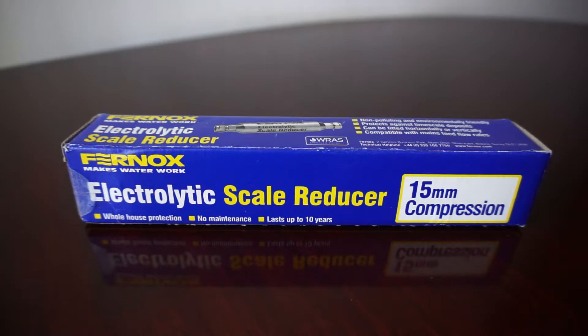In the search of a solution to reduce the scale produced by the water here, I came across this brand, the Fernox one. I purchased what I thought initially would be a magnetic filter, which would be able to replace the usual ones — the cheap ones that really have nothing to do with scale reduction. The scale forms itself on the pipes and inside the heat exchanger of the boiler like I would not have any magnetic filter whatsoever.